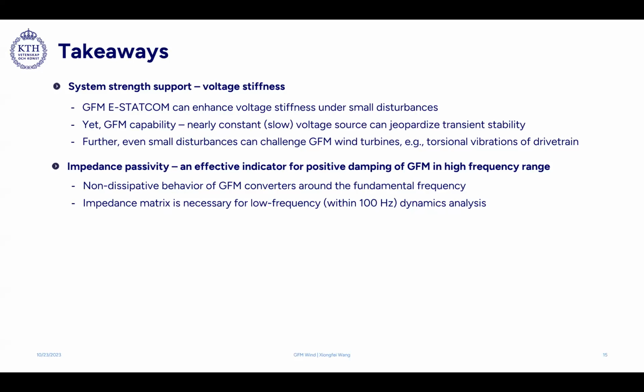This is based on our interactions with TenneT or other TSOs. But within 100 Hertz, we have to respect the non-dissipative behavior of the grid forming converters. And we also need to use the impedance matrix to analyze the system stability. Yeah, the last point is quite clear. I don't want to repeat it.